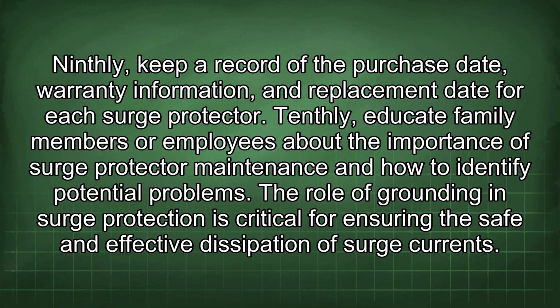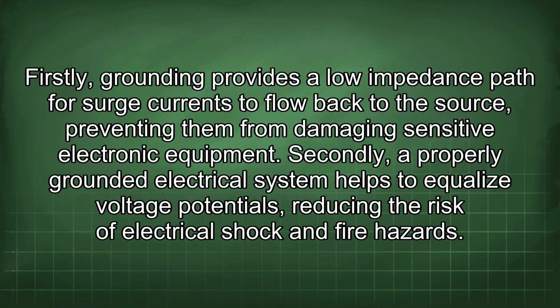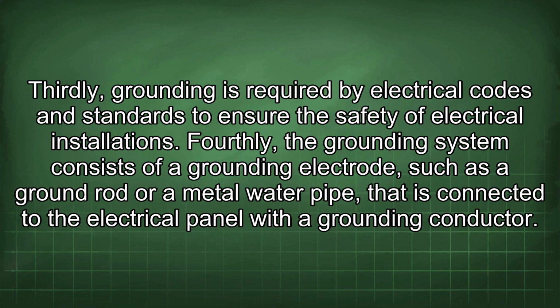The role of grounding in surge protection is critical for ensuring the safe and effective dissipation of surge currents. Firstly, grounding provides a low impedance path for surge currents to flow back to the source, preventing them from damaging sensitive electronic equipment. Secondly, a properly grounded electrical system helps to equalize voltage potentials, reducing the risk of electrical shock and fire hazards. Thirdly, grounding is required by electrical codes and standards to ensure the safety of electrical installations.